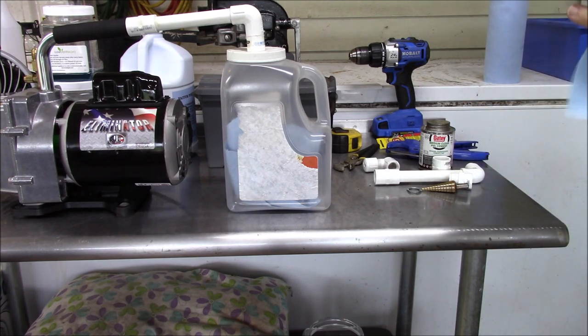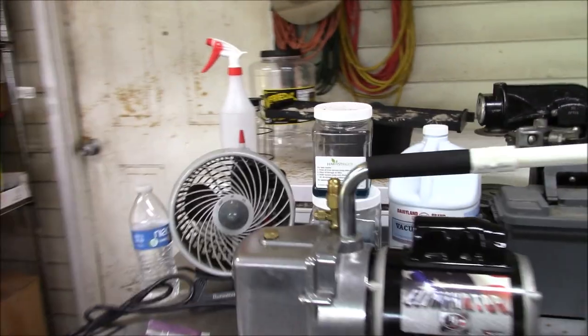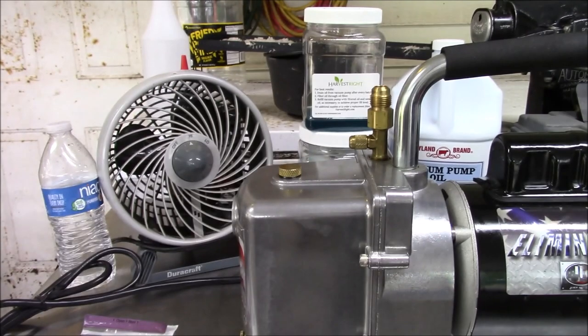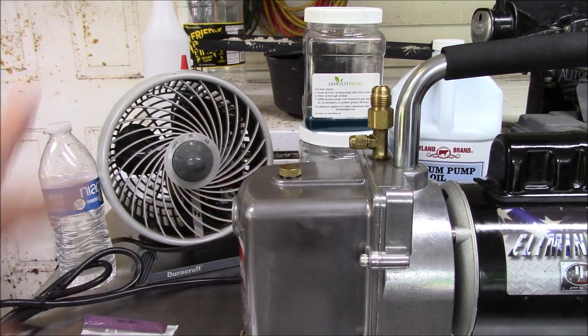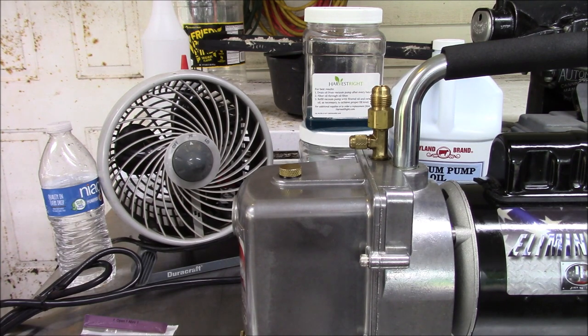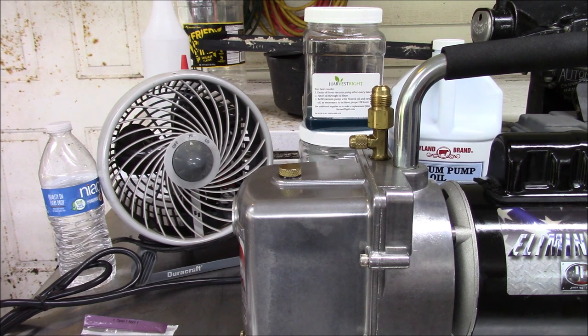I didn't mean to get so long-winded. One other thing, before we forget, the fan. Always keep a fan running on this piece right here. You want to keep that cool. Just a little small fan, really not much. And you keep a fan blowing that, because that's the lifeblood of this pump, is keeping it cool. With that said, this is Technician 775, the reliable prepper. Please subscribe, and hit the like button if you like what we've done. And if we did something wrong, let us know. We'll be more than glad to redo the video. Thanks again.